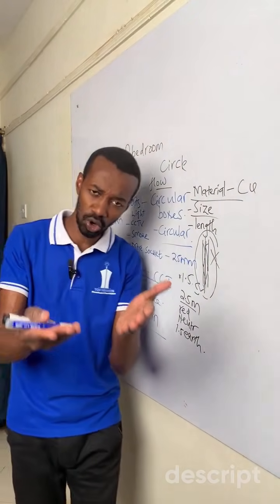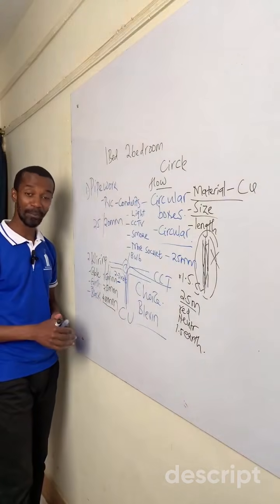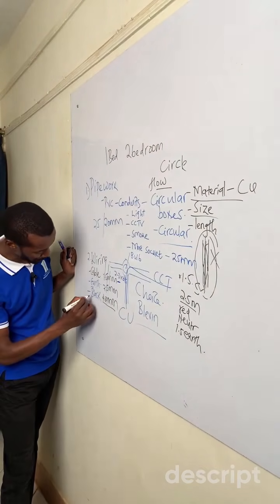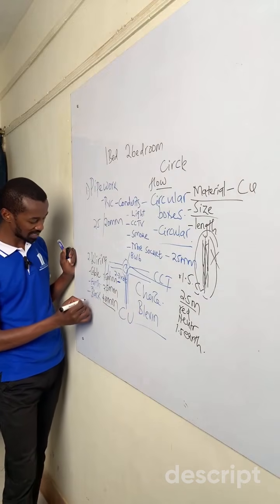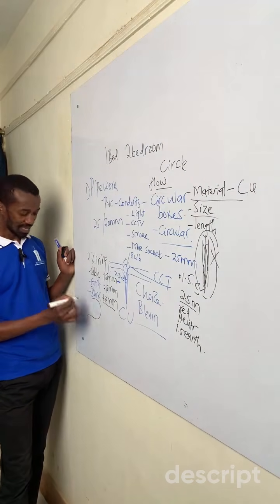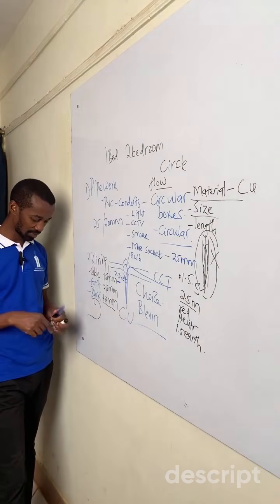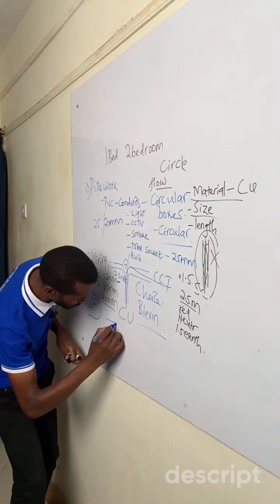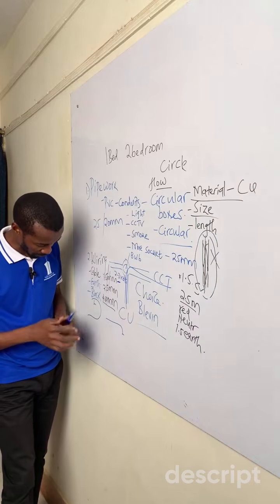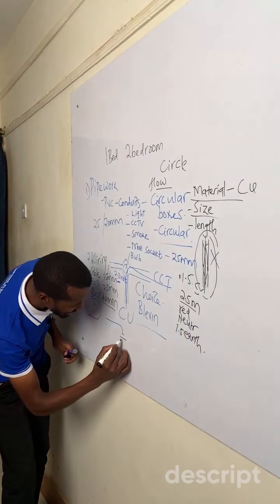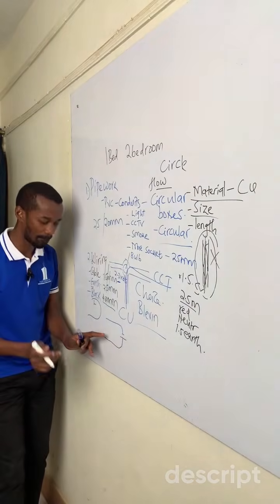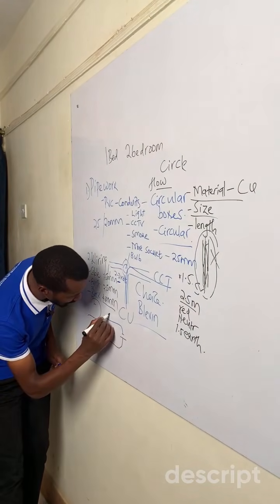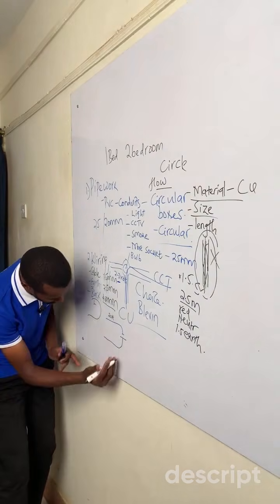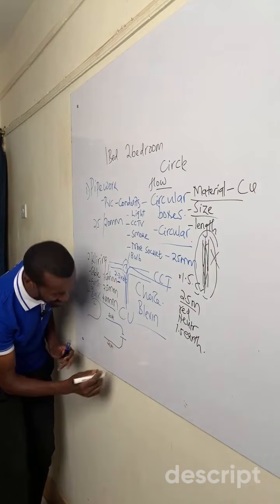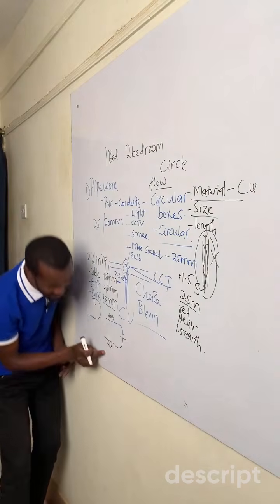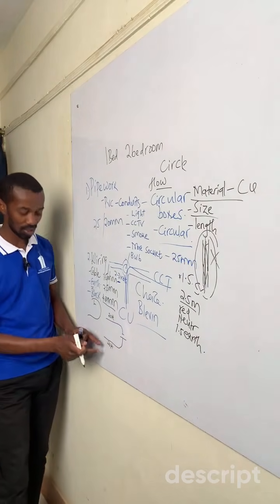But again you may ask, John, why 4.0? Remember the reason we have a black cable or neutral cable is simply because it acts as a return. The current flowing through the line, let me use the red, to whatever appliance or device, could be the shower, is the same current flowing back to the source. So if what is flowing here is 20 amperes, know that what will be flowing back is also 20 amperes. The main question is, will this return path, the black cable, be able to handle 20 amperes?